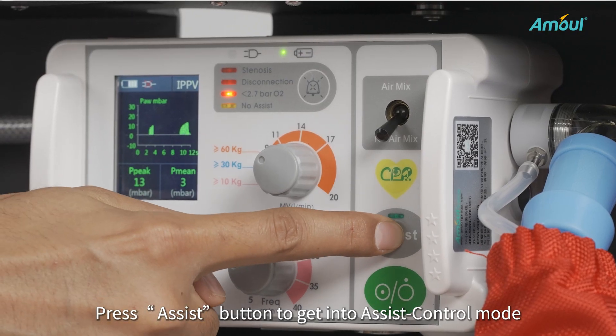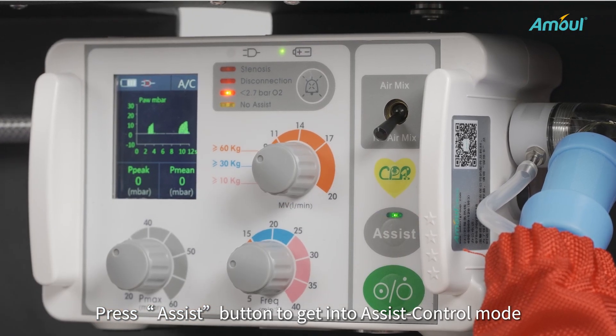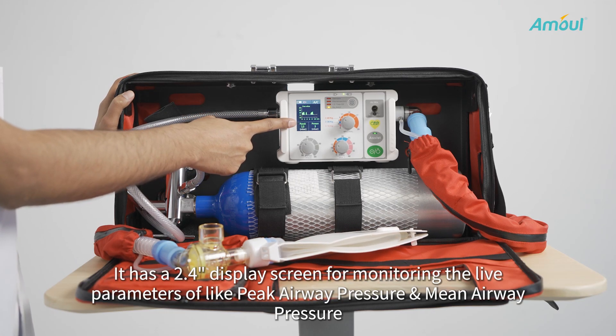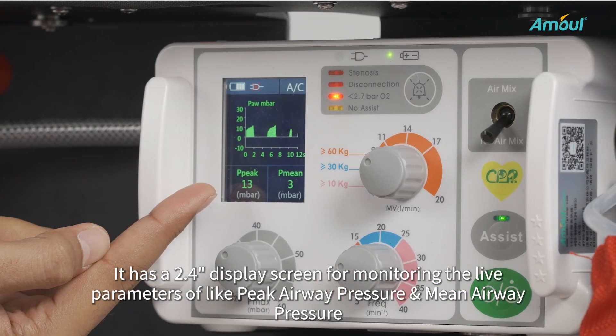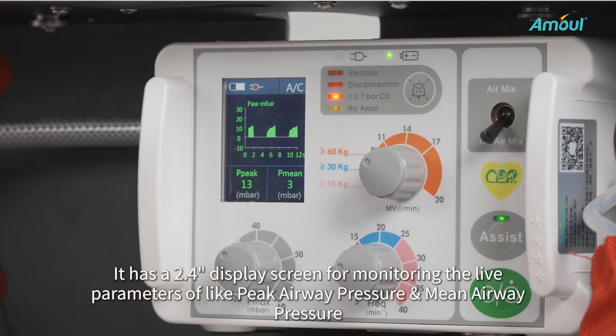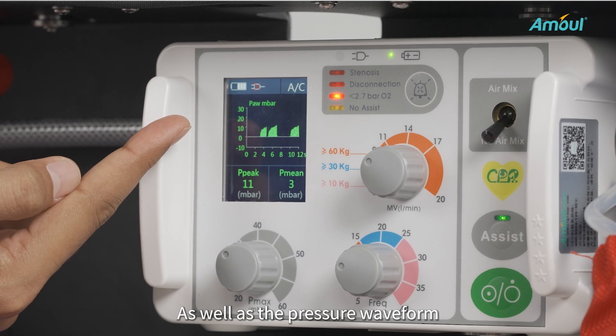Press the ASSIST button to get into ASSIST control mode. It has a 2.4-inch display screen for monitoring live parameters like peak airway pressure and mean airway pressure, as well as the pressure waveform.